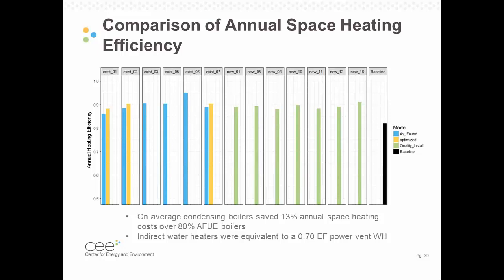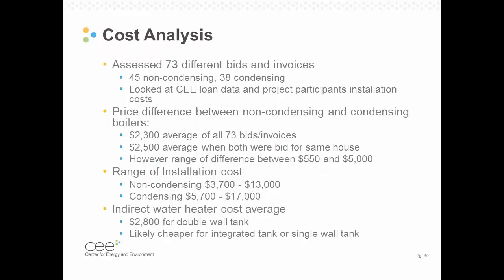And what you can really see here is that all of these boilers performed at about that 90% level. And based on utility billing analysis and some characterization of 80% boilers that we had, we saw that this was about a 13% savings on the space heating side across all these buildings. On the water heating side, we noted that the power vent on these boilers was performing much like a power vent water heater in terms of efficiency.